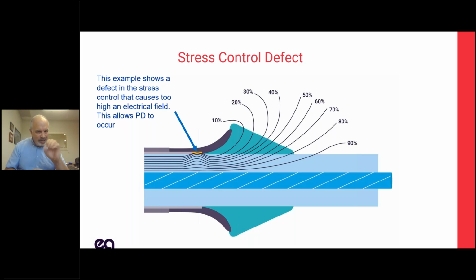So I'm going to start getting arcing inside that cable. I'm not going to see anything from the outside. I may or may not hear something, depending on how close it is to the outside, but I'm going to get this discharge, and I'm going to get it from the day that thing is energized till it finally fails. So this is how the stress control relates to the failures.